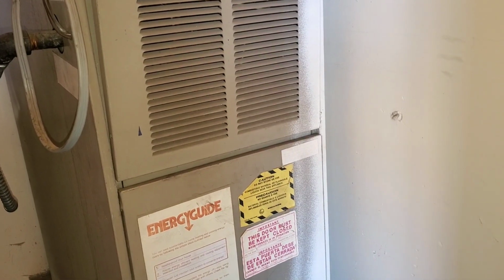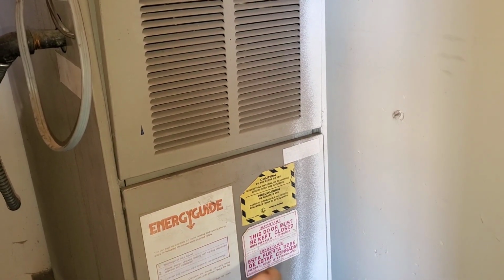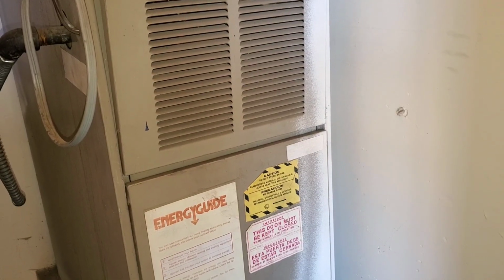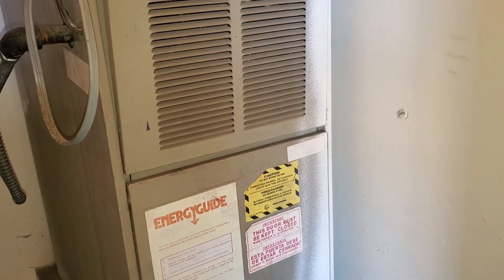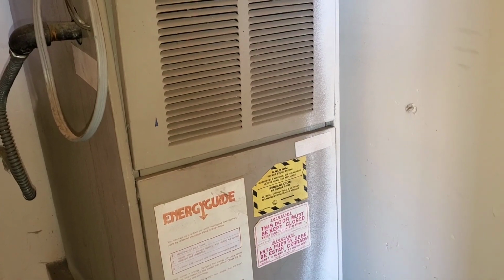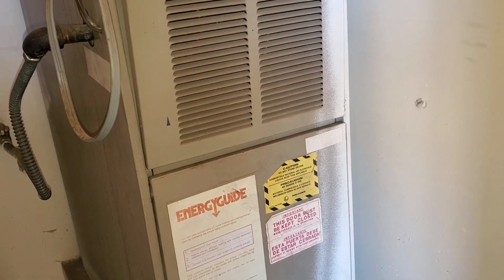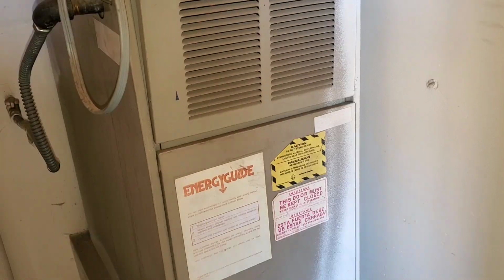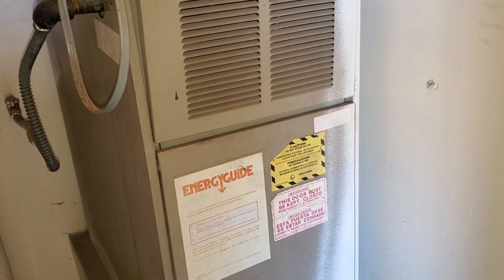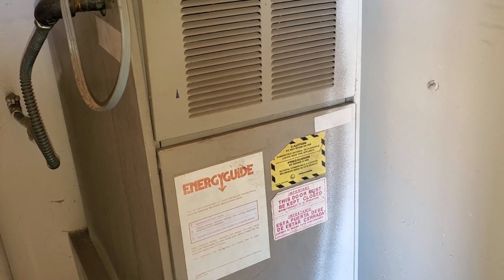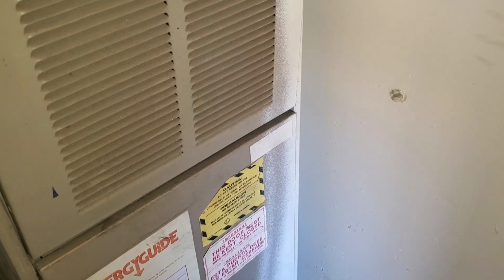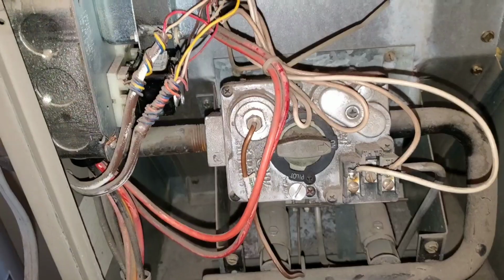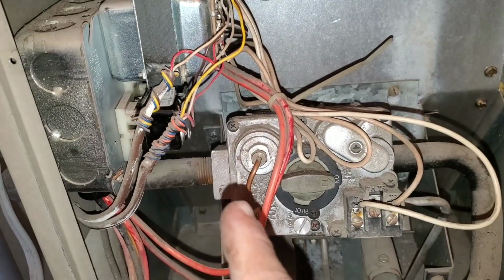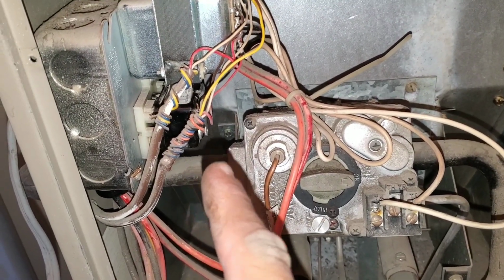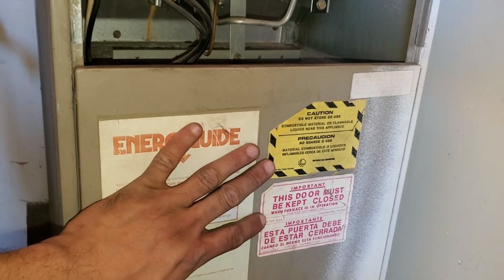Once you set your thermostat, step two is going to be to find out where your blower motor, your transformer, and your relays are located. It may be in a water heater room, it may be in a hallway, it may be in the attic. At this point, step two, you're going to see if your blower motor turned on. Right now, just for visual observation, I'm going to remove my panel. This is where my transformer and my relay are located. I'm going to remove my door.